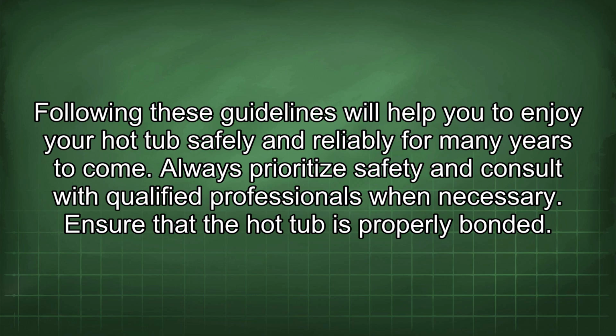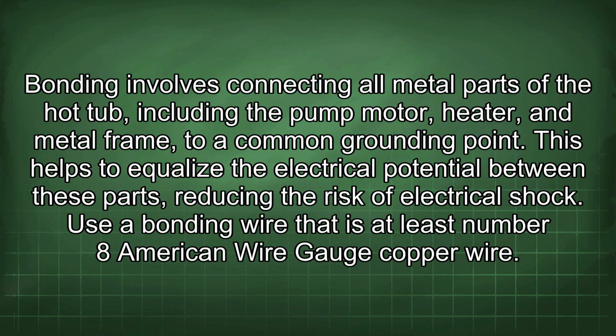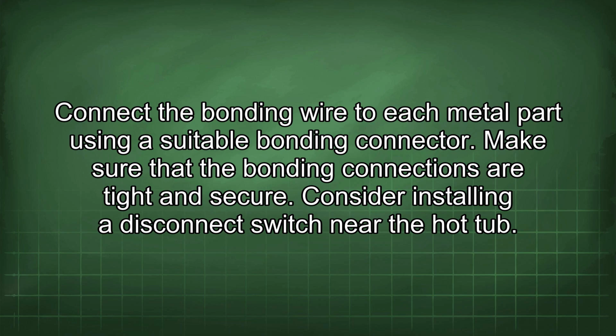Ensure that the hot tub is properly bonded. Bonding involves connecting all metal parts of the hot tub, including the pump motor, heater, and metal frame, to a common grounding point. This helps to equalize the electrical potential between these parts, reducing the risk of electrical shock. Use a bonding wire that is at least number 8 American wire gauge copper wire. Connect the bonding wire to each metal part using a suitable bonding connector. Make sure that the bonding connections are tight and secure.